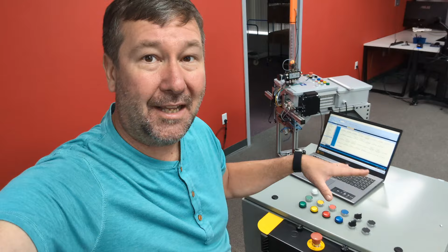This one right here is not working. Oh wait, I forgot - on this one, while we have the safety inputs, I wanted to show how to troubleshoot e-stops that are wired in series. I know a lot of y'all are saying don't wire them in series, but we still need to be able to troubleshoot them when they are. So if I press this e-stop, that drops out, pull it back out. Or if I press this other e-stop, that drops out too. So it was working, I just couldn't remember how to do it.